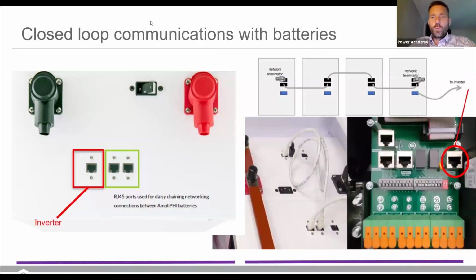We're looking at closed loop communications for SimpliPhi batteries here. On the SimpliPhi batteries, or our 4.9 batteries, for the closed loop communications there are two sets of ports. There's a device port, and these are labeled on the batteries. I'm showing a battery without stickers on it here, labeling them. The device port is used to connect to the inverter, and then the battery CAN bus ports are used for daisy chaining. You never want to have a battery port that's open.